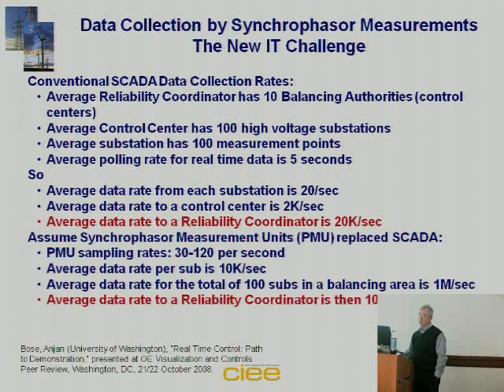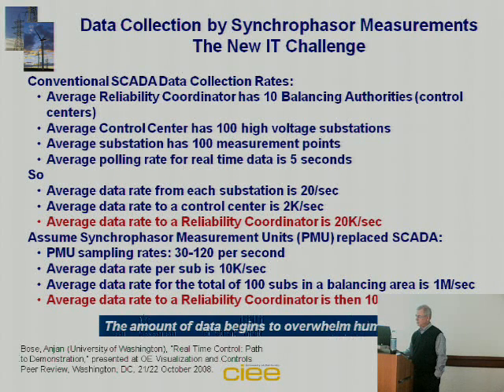This is where we're heading: assume that synchrophasor measurements replace all SCADA, which is a bit of a gross assumption, but for the purposes of putting a magnitude on this. PMU sampling rates are between 30 and 120 times per second, meaning the average data rate per substation is about 10,000 data points per second. For 100 substations in a balancing area, that's about 1 million data points per second, and a reliability coordinator ends up dealing with 10 million data points per second. This is certainly reaching oversaturation for a human being's ability to handle it.